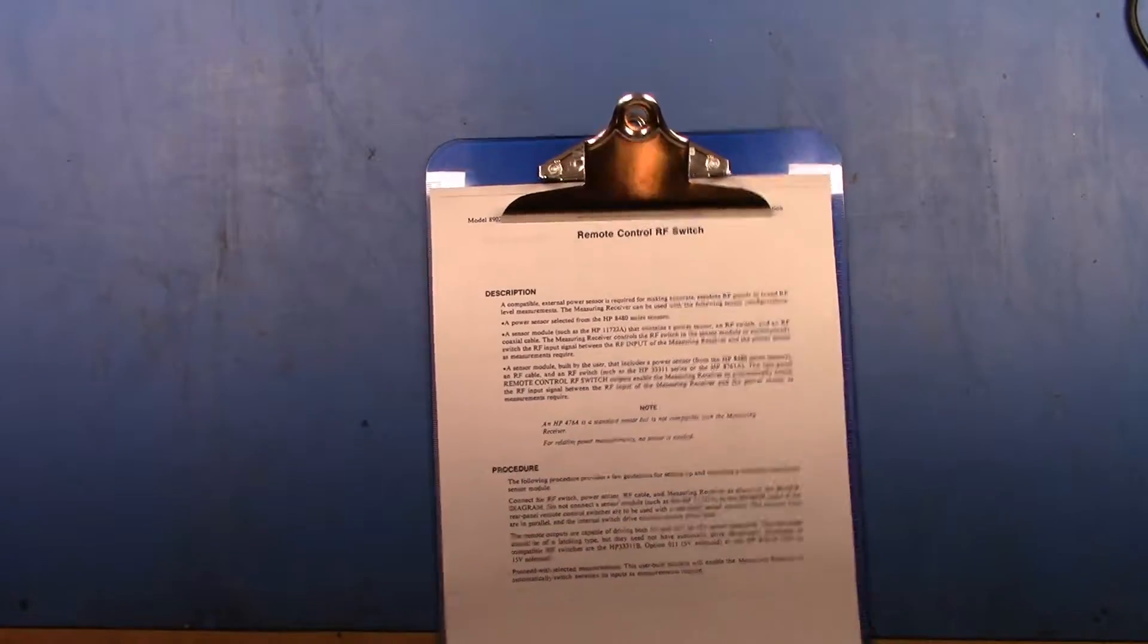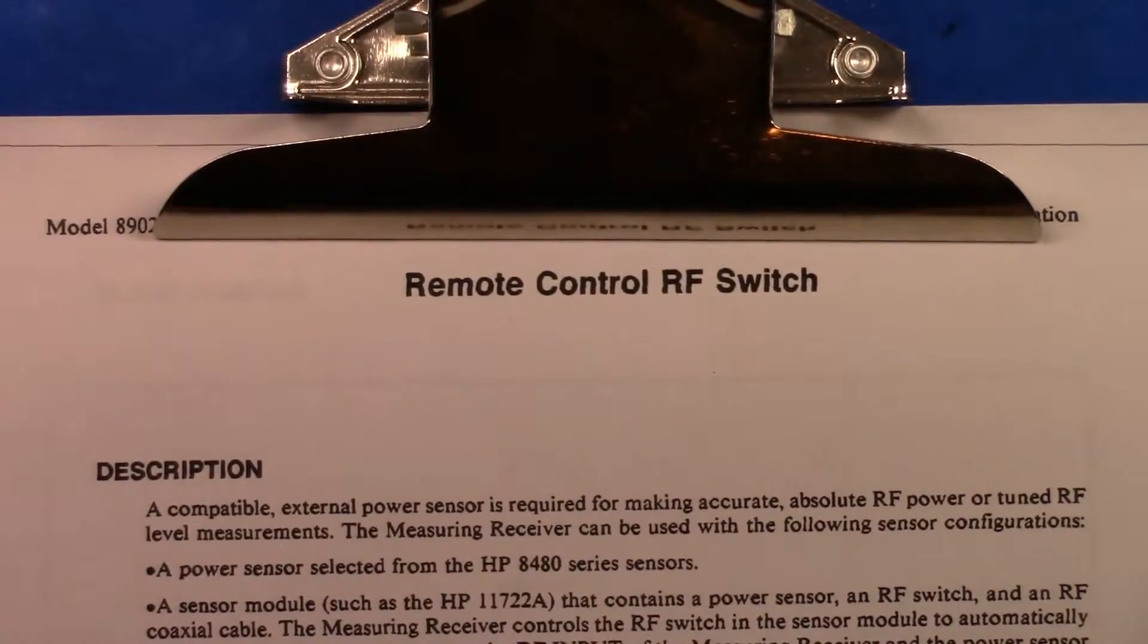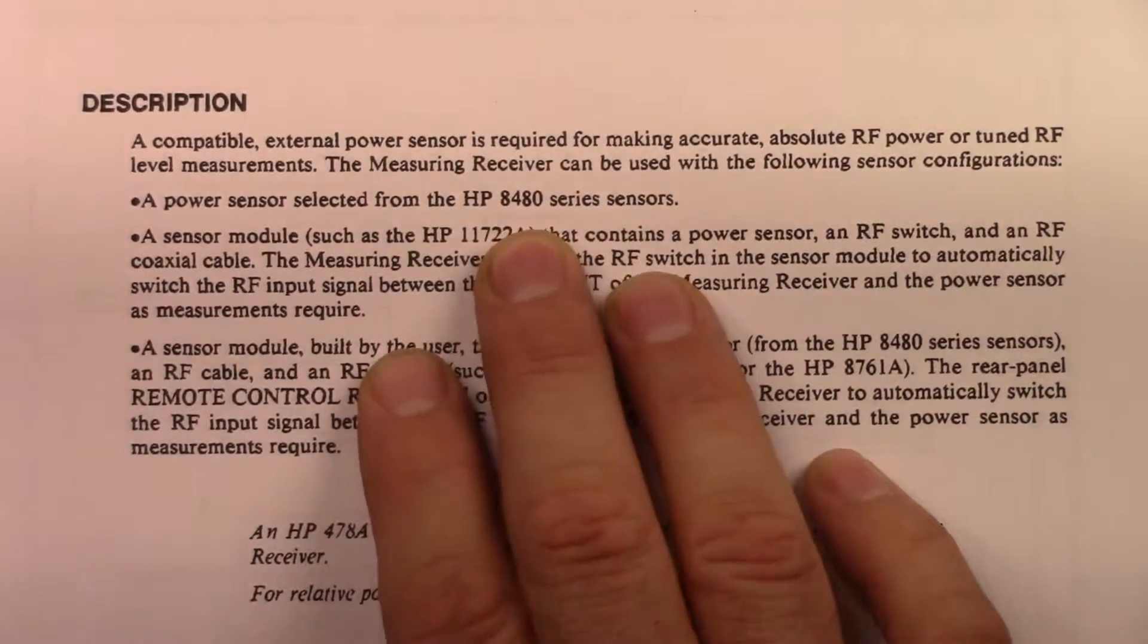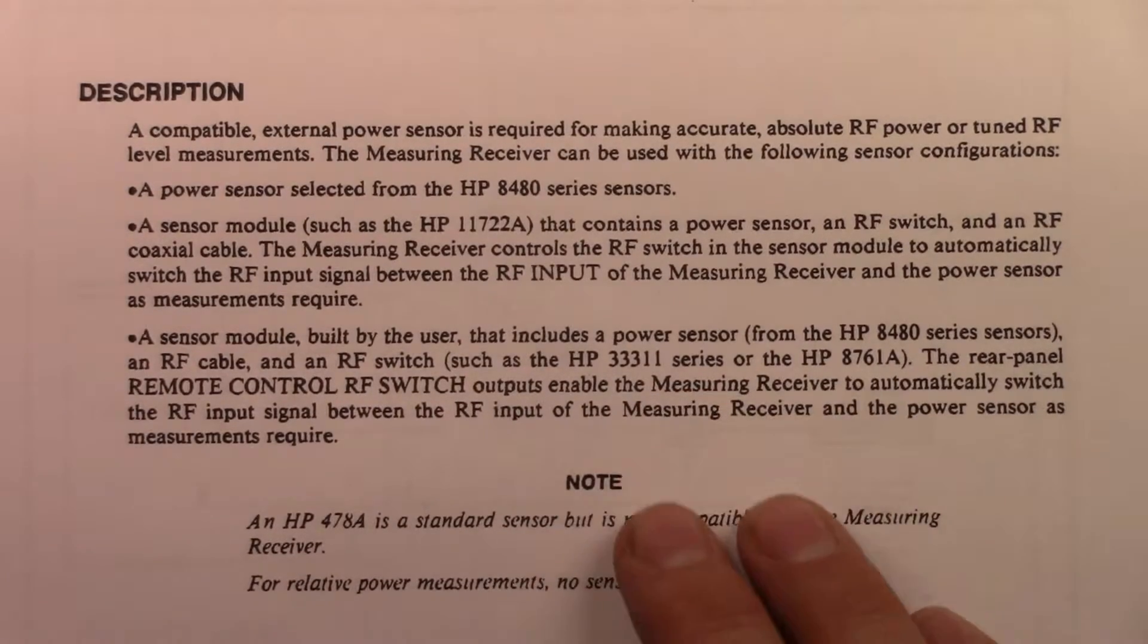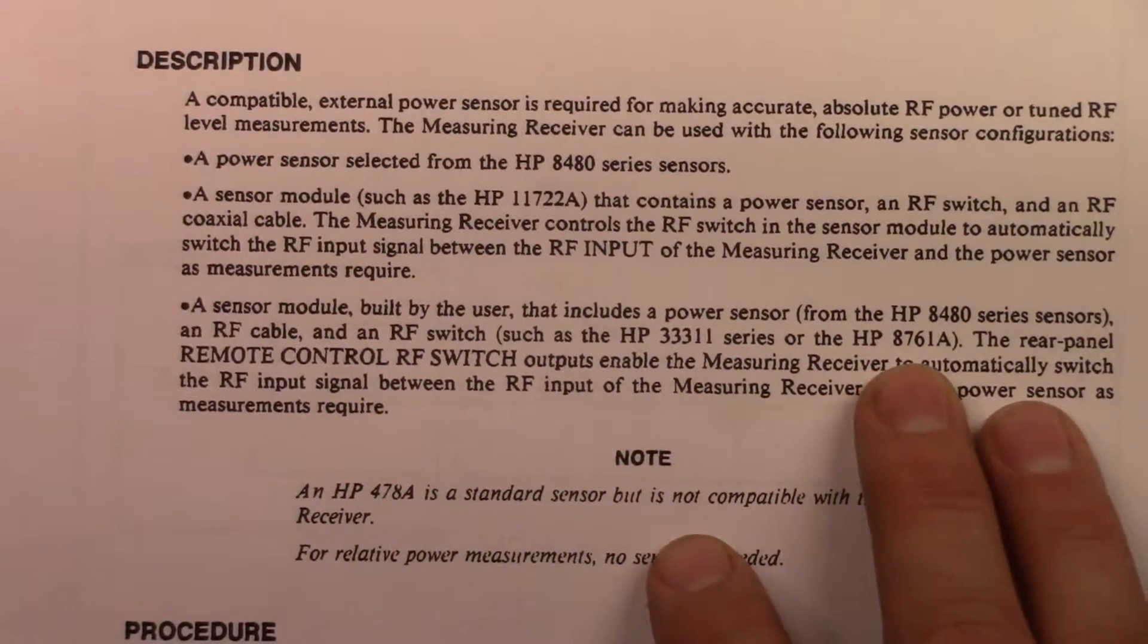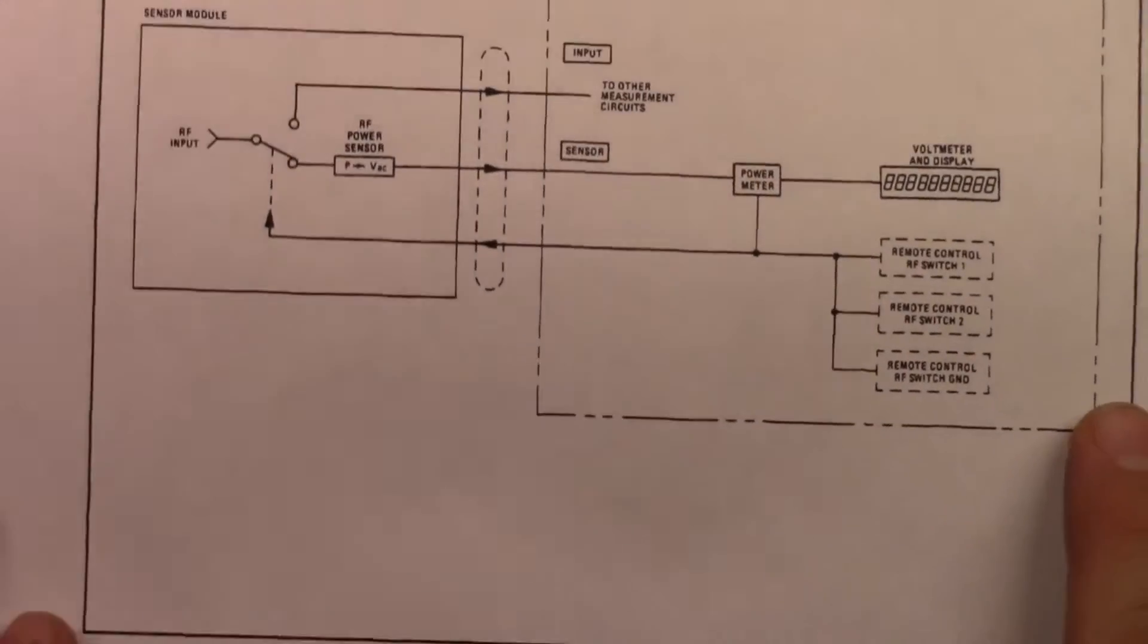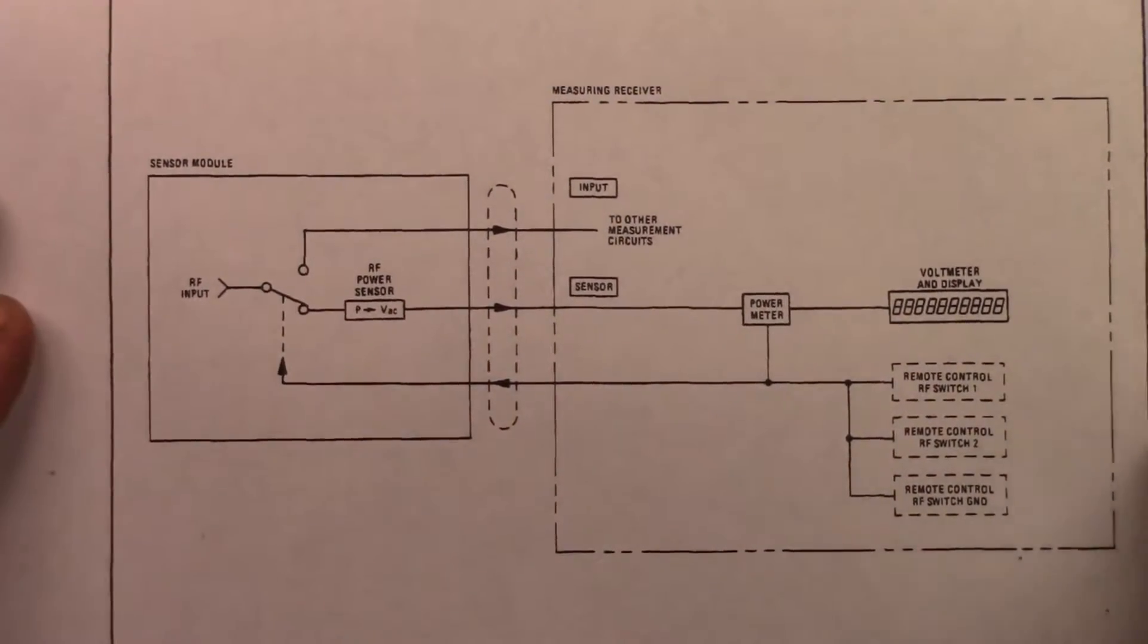Here is the relevant section out of the manual. Let me zoom in a bit so that we can see this. It's about building a remote control RF switch and it goes through to describe what it is and the type of power sensors that you need. So you need something from the 8480 series of sensors. You need a switch and the switch needs to be capable of dealing with the power that comes out of the back, so either a 33311 or an 8761A. And then there is a procedure that you can follow and effectively a little diagram that shows you how the sensor works. And this is effectively exactly how the 11722A sensor works.